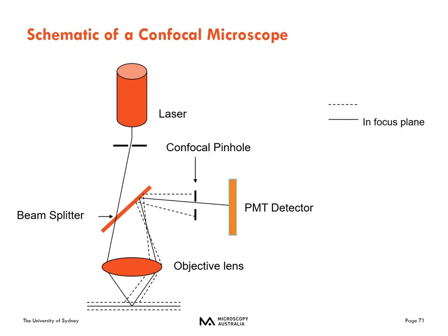Here is a very basic schematic of a confocal microscope. You can see that we've got a laser as our light source directing light through a beam splitter — that's the same as the dichroic mirror filter cube we talked about earlier — through the objective lens. You can see that it's still exciting throughout that full volume, just like a wide field microscope. However, as the light passes back up through the objective, those fluorescence emissions get bent, just like a fluorescence microscope. But those out-of-focus planes get blocked by the confocal pinhole, and only the light from the focal plane is allowed to reach the PMT detector.